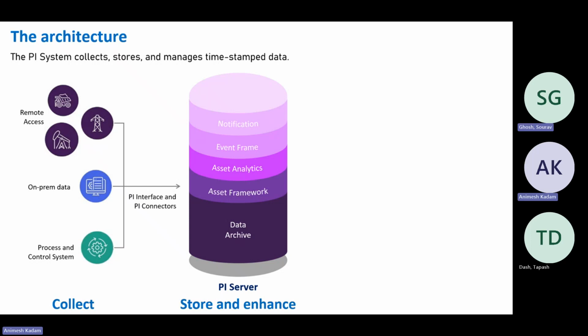Yeah, so that's what I'm saying, the asset framework, the templates, the event notifications or event configurations. Everything: the asset framework, analysis, tables, notification, event frames, everything will be in SQL. So even the configurations will be stored in the SQL. And even PI Vision: the entire detail about PI Vision and the screens will be stored inside the SQL.